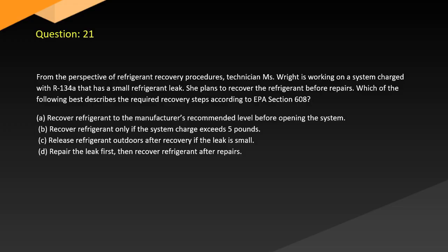Question 21. From the perspective of refrigerant recovery procedures, a technician is working on a system charged with R-134a that has a small refrigerant leak. She plans to recover the refrigerant before repairs. Which of the following best describes the required recovery steps according to EPA Section 608? A. Recover refrigerant to the manufacturer's recommended level before opening the system. B. Recover refrigerant only if the system charge exceeds 5 pounds. C. Release refrigerant outdoors after recovery if the leak is small. D. Repair the leak first, then recover refrigerant after repairs.